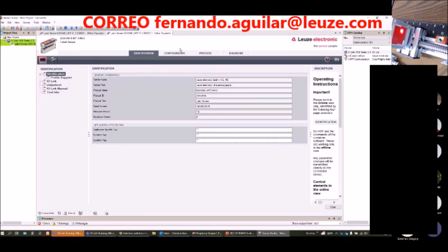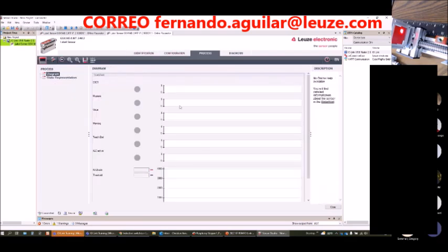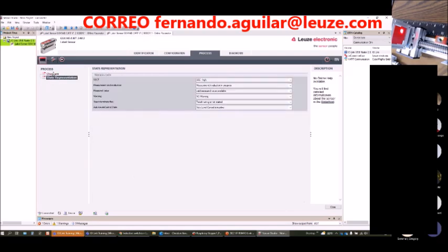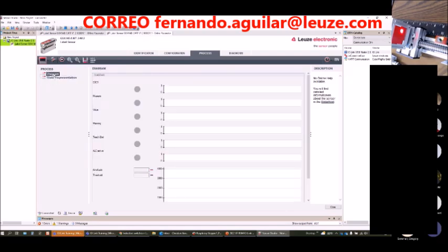And traditionally, when you had analog sensors in the past, now you can use IO-Link enabled digital devices and get rid of all the analog concerns, like having to have shielded cables, or strange lengths, or ground loops, or all these other problems that are created when you have the need for shielded products. So you're automatically switching to a digital conversion right at the device, right at the sensor or whatever device it is that's being looked at.